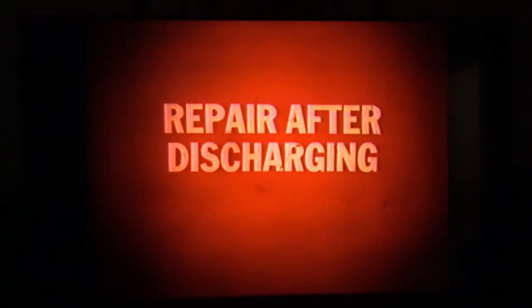System components can now be removed for repair or replacement. In this case, the receiver dryer will be removed and replaced by a new unit. Cap each hose as it is removed from the old receiver dryer unit. Do not remove the caps from the new receiver dryer unit until you are ready to connect each hose.